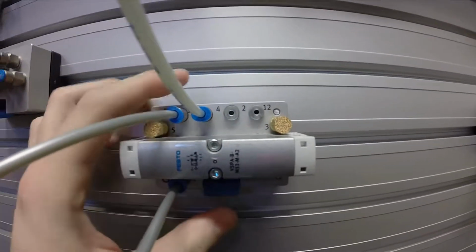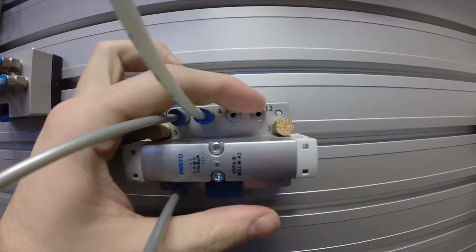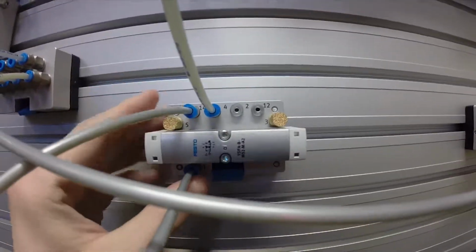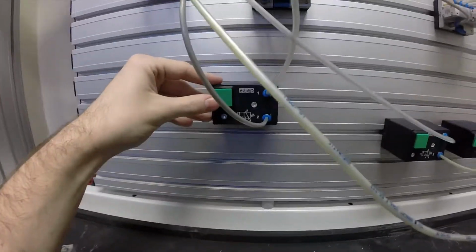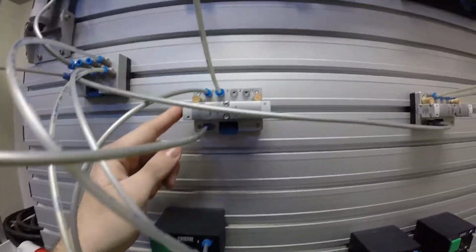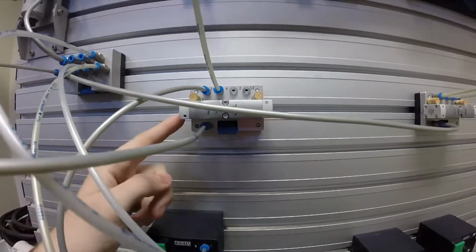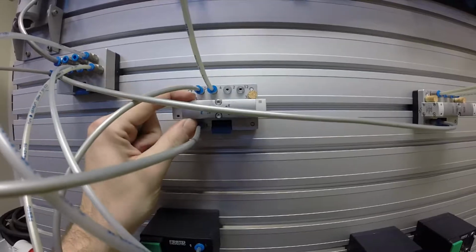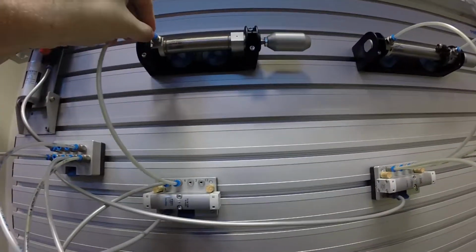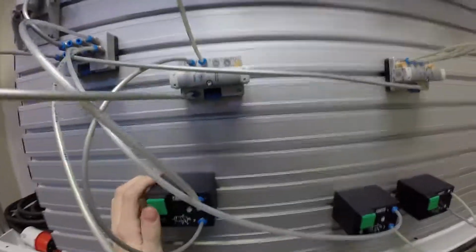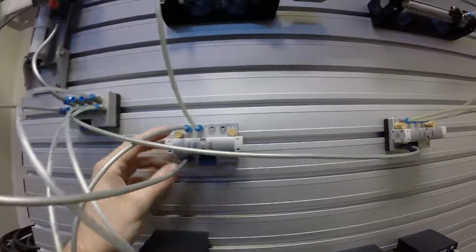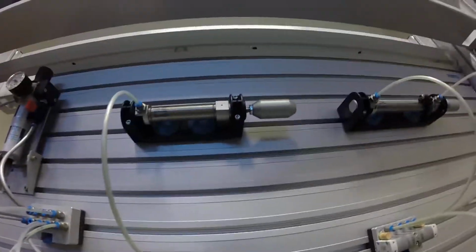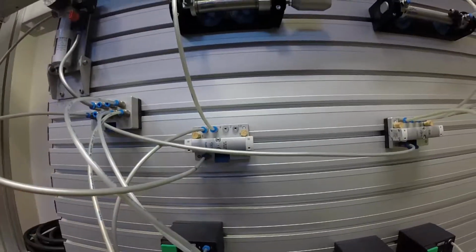And these are customizable valves. You see here we can unscrew these and tap in on them and change it to maybe a 5-2 valve. But for the moment we're indirectly controlling this. The push button valve is going to allow air to flow in on this, and then the air pulse from this original valve is going to change this 3-2 valve here, which will then operate the cylinder. So our input could be much further down the line, operates our 3-2 valve by a pilot line, and then it operates our single acting cylinder.